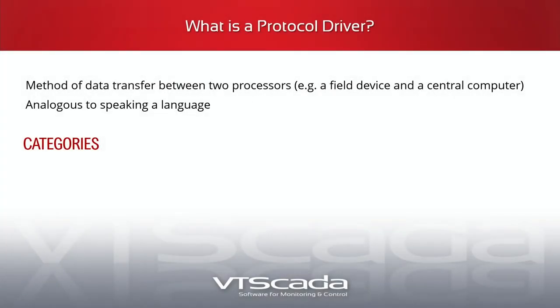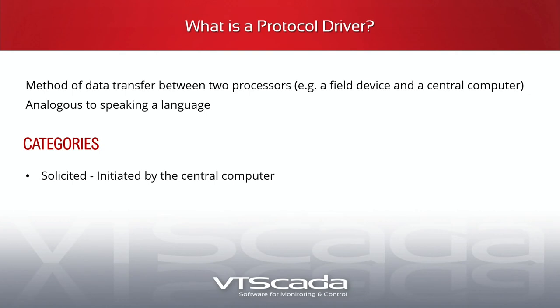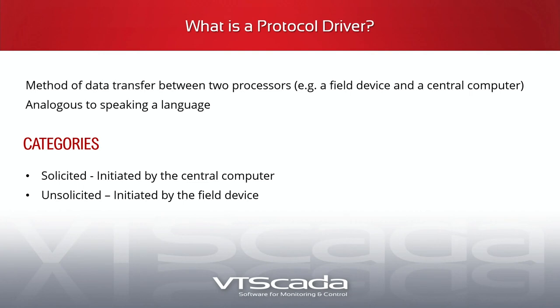The comm driver is the next piece — I like to say it's analogous to a language. Each device typically talks a language, and we have to be able to speak a whole bunch of different ones. Categories: solicited, which is initiated by the computer — it polls the device in the field, which hopefully talks back. Unsolicited, where you don't talk to the device but wait for it to talk to you. And advanced protocols, which can be solicited plus unsolicited plus additional capabilities — which is why there are so many protocols.